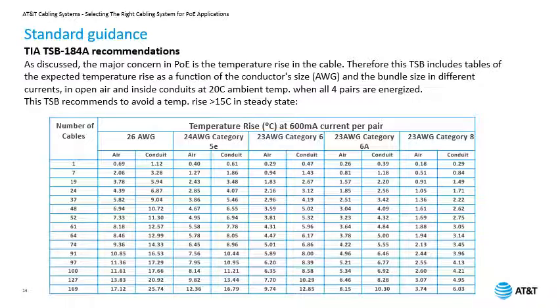In addition, you can see clearly that cables inside the conduit will be affected more by temperature elevation in comparison with cables left in the air. Therefore, TSB recommends avoiding any temperature rise above 15 centigrade in steady state.